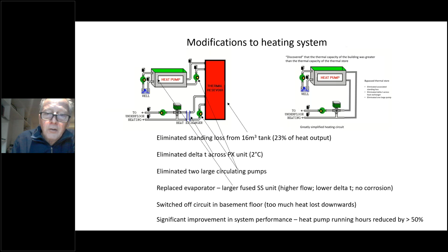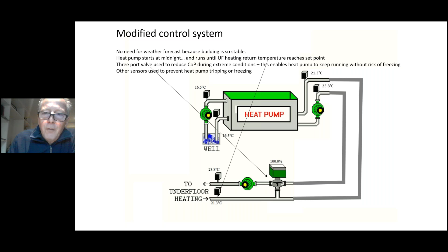We also switched off the circuit in the basement floor because we found there was too much heat being lost downwards. And when we'd made all those modifications, the system operated significantly more efficiently. In fact, the running hours dropped to less than 50%. We modified the control system because we found there was no need for weather forecast because the building itself was so stable. So we now start the heat pump running at midnight, and it runs until the building reaches its set point. We have a 3-port valve in the system that enables us to deliberately reduce the COP of the heat pump and therefore avoid the risk of freezing in the evaporator.